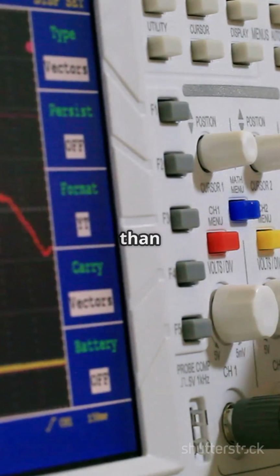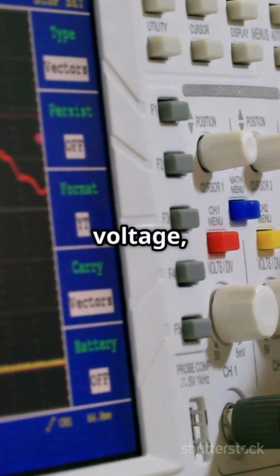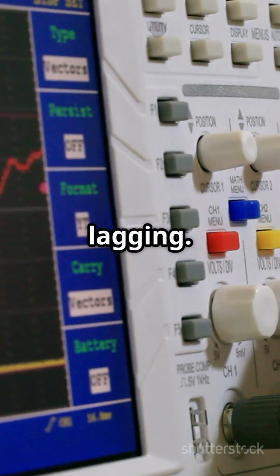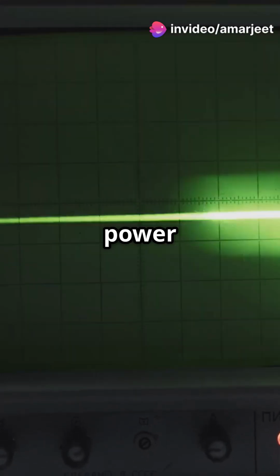To determine whether the power factor is leading or lagging, observe the sign of the phase angle. If the phase angle is greater than 0, the current lags the voltage, which means the power factor is lagging. If the phase angle is less than 0, the current leads the voltage, indicating a leading power factor.